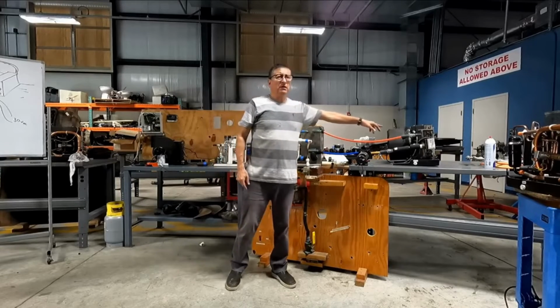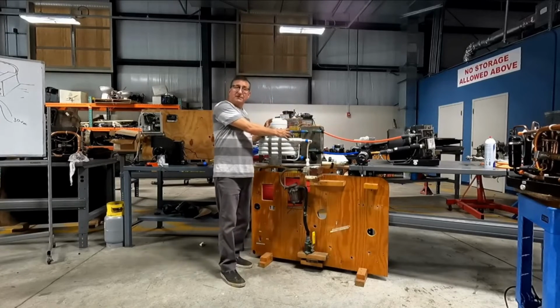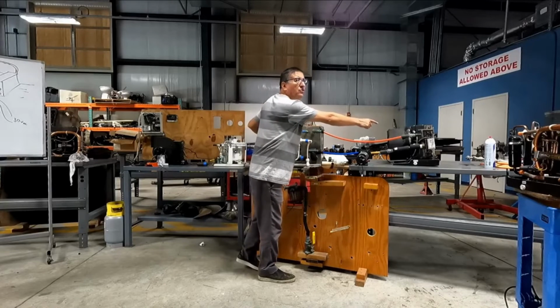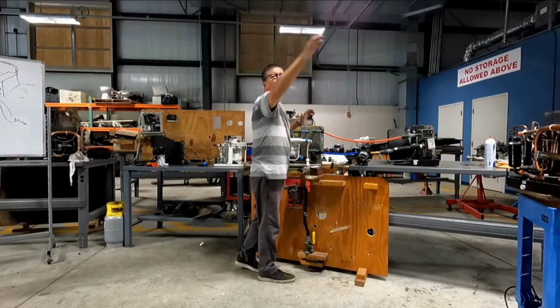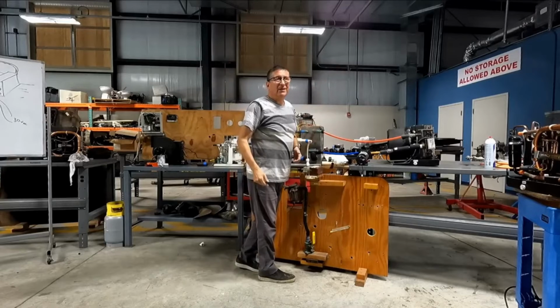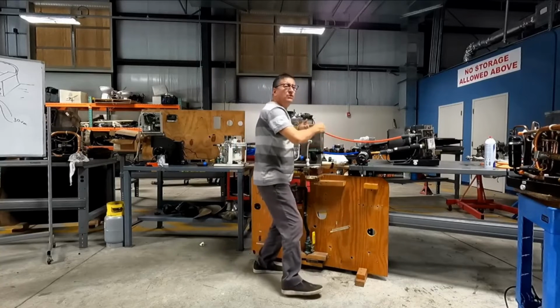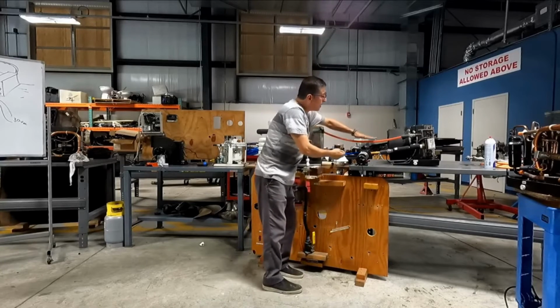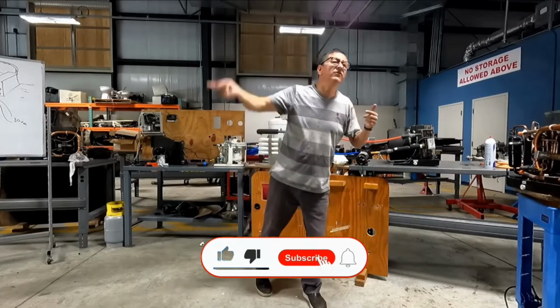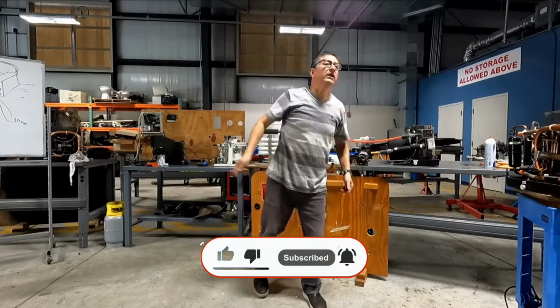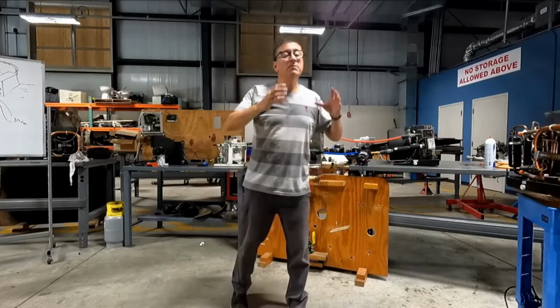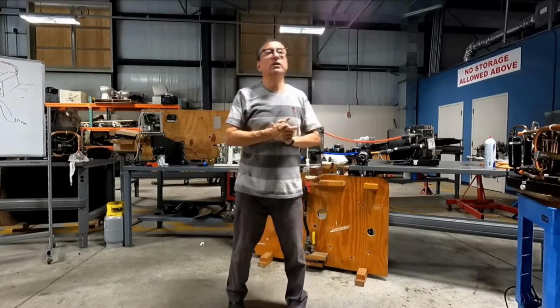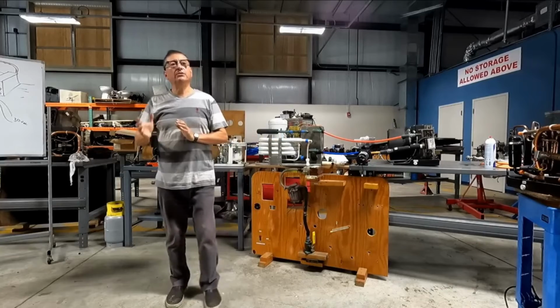In some cases, with one unit like this, how many air handlers do you have? Four, six, ten, twelve. In that case, you need one pump to move in this direction, and another one to return. You have one here and one here, two circulating pumps. It's to improve the movement of the coolant. And it would be the same size pump for each side, the same pressure and the same flow. That's correct.